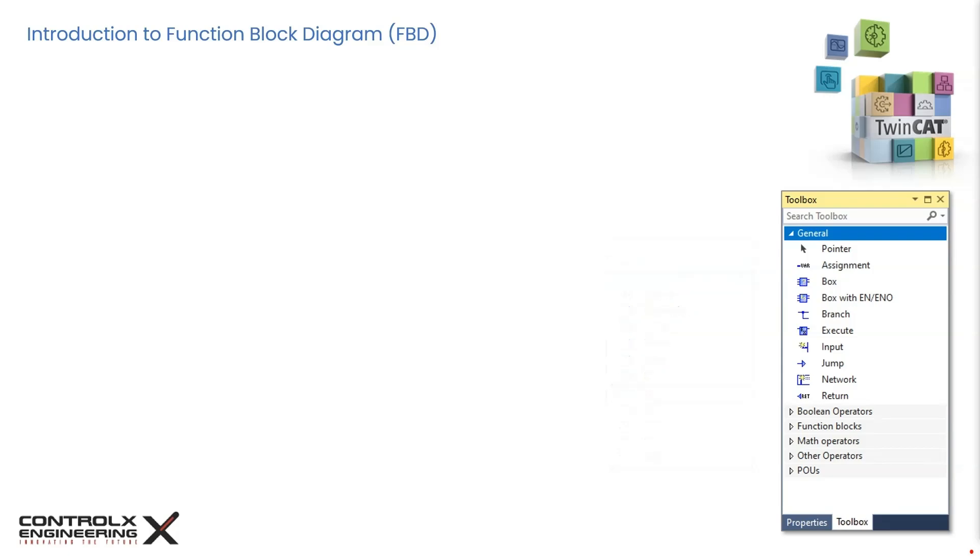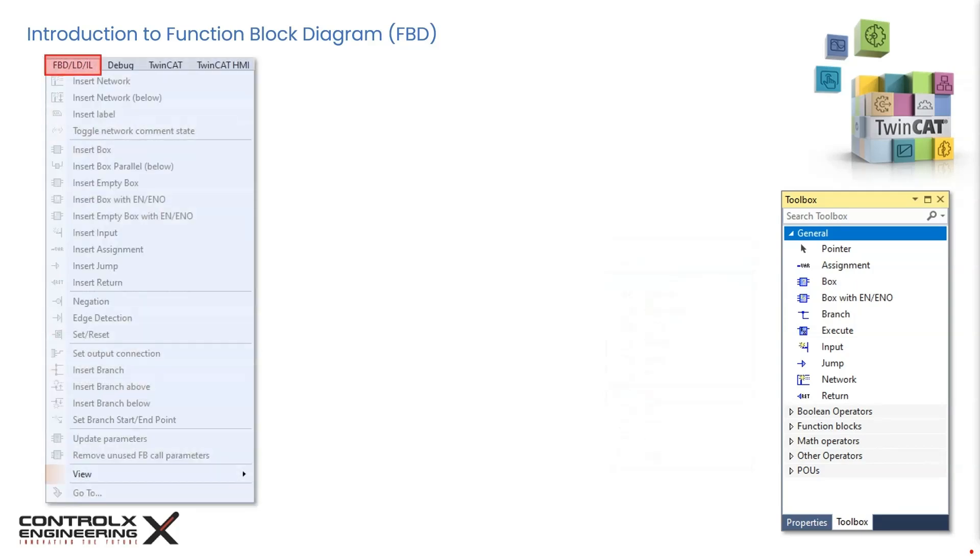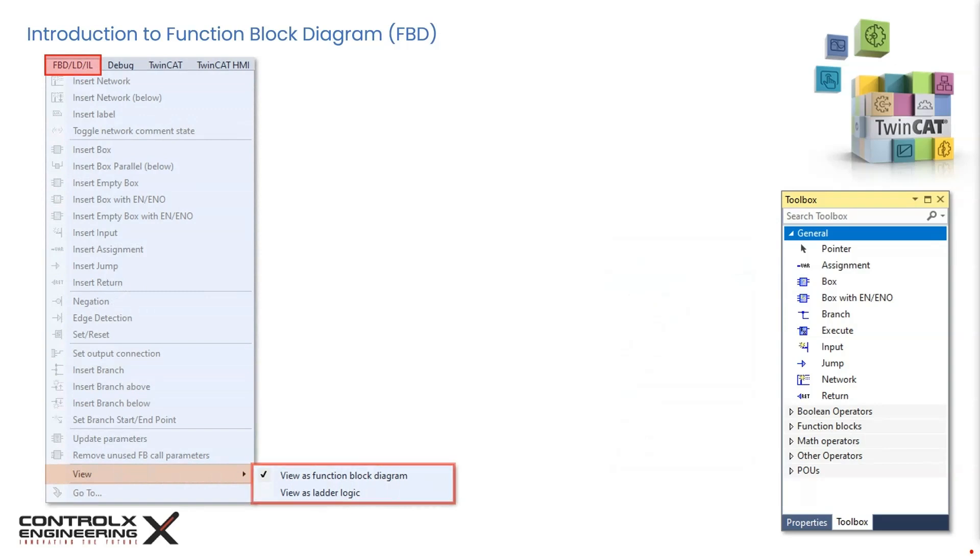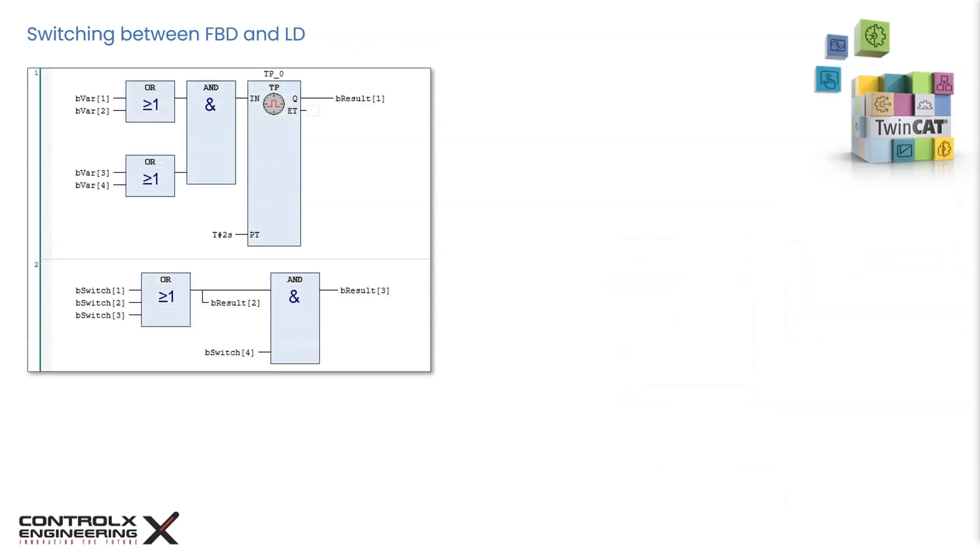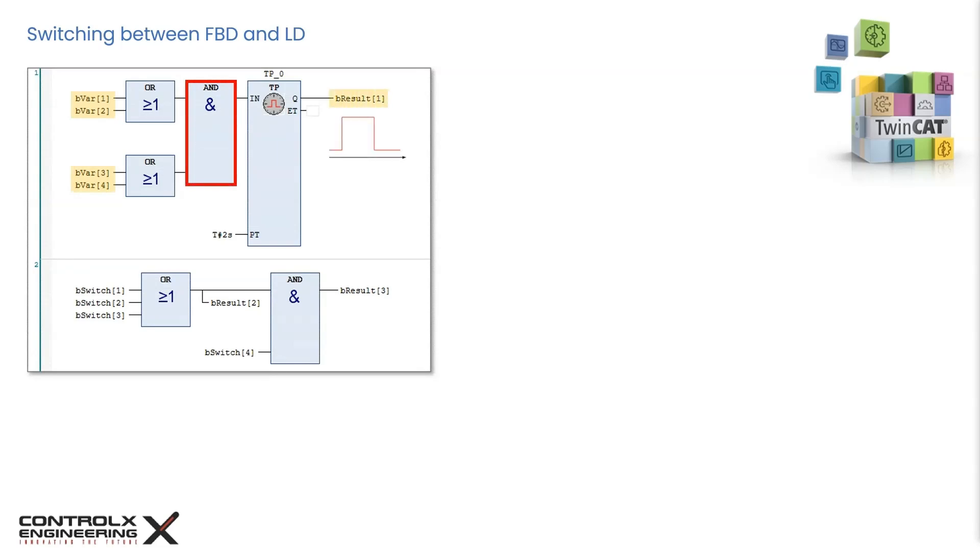The code is structured into networks and can be interchanged freely between the FBD and LD implementations. For example, the ladder diagram can be converted to FBD and vice versa using this option from the FBD LD IL menu. Here is an example of a simple FBD program that is executing Boolean logic to turn on some output bits. In the first network, either of these two input bits or conditions must be true, and either of these two input conditions must be true, which satisfies the AND function. This triggers the pulse timer and the output bresult1 becomes true for 2 seconds.